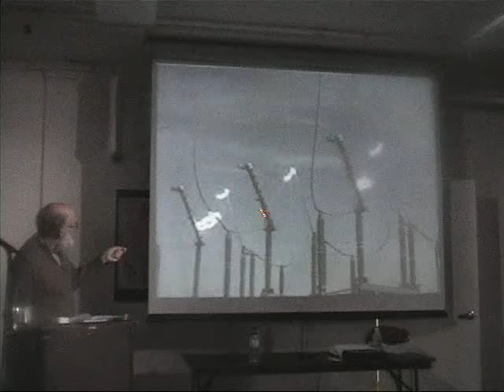And what I just read from Steinmetz is, in the actual arcs where the switch contacts are breaking open, you start to get energy anomalies in these arcs. And the system goes into a cumulative oscillation and continues to accumulate energy until something blasts.